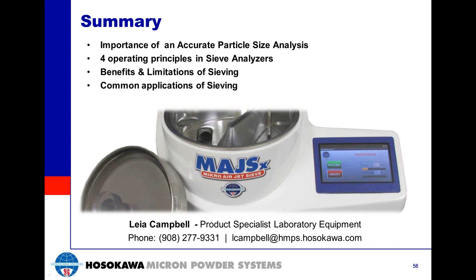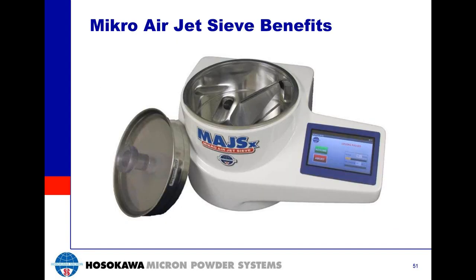Is it possible to use more than one sieve at a time on the MAJS-X? No — the Airjet sieve is designed for the test sieve screen to sit down inside the housing, and you would not use more than one at a time. You start with the finest sieve screen first to eliminate cohesion or agglomeration. What's the smallest particle size range you can handle? We can comfortably handle down to 20 microns. We do offer 5, 10, and 15 micron nickel-edge sieve screens, though these are more expensive and require extra care; their suitability depends on the material.